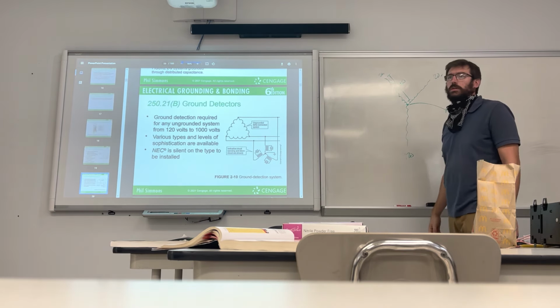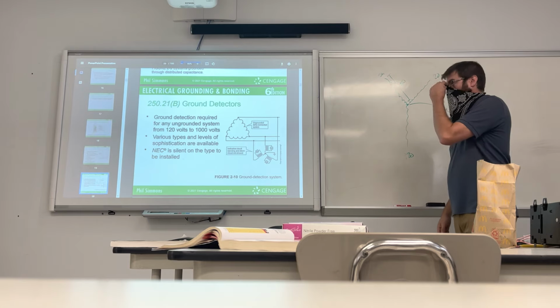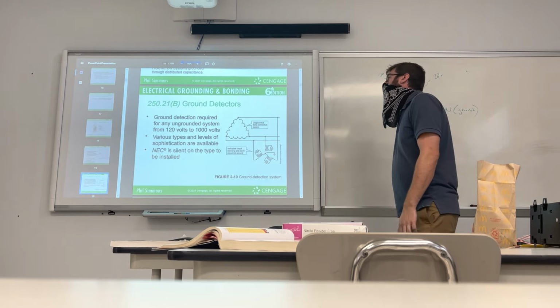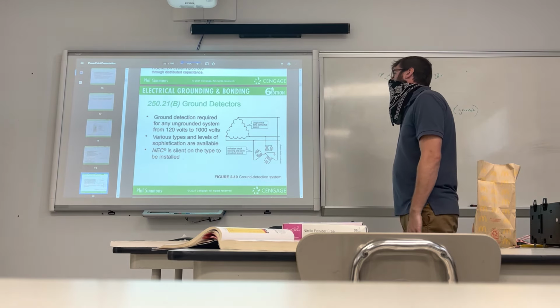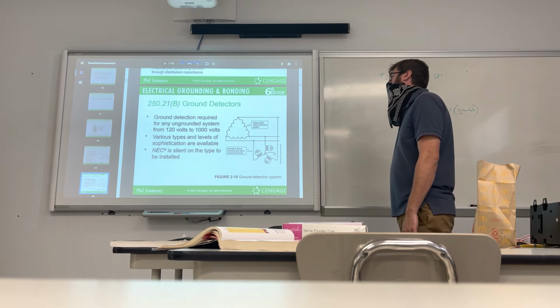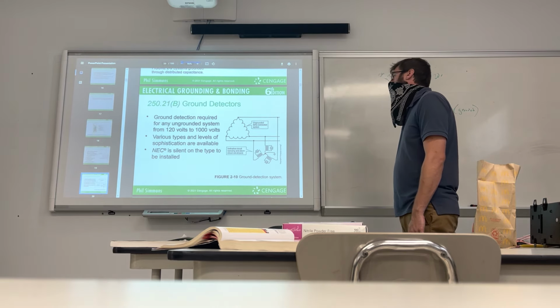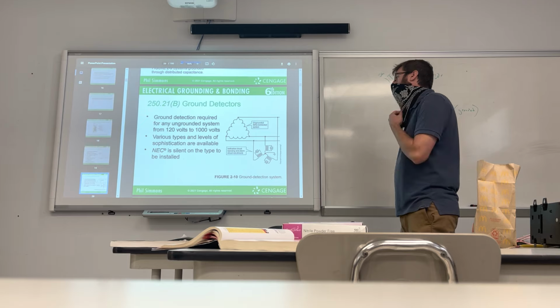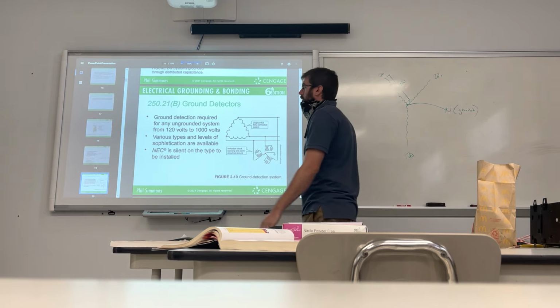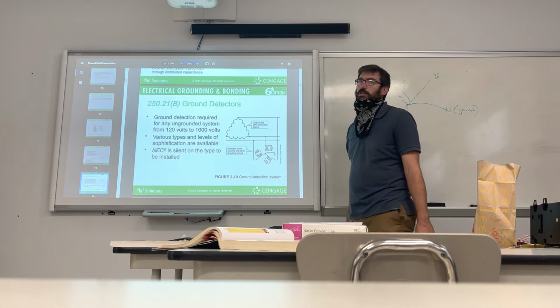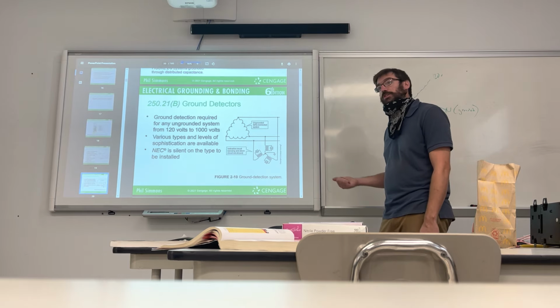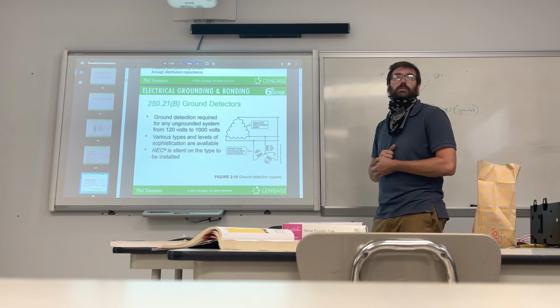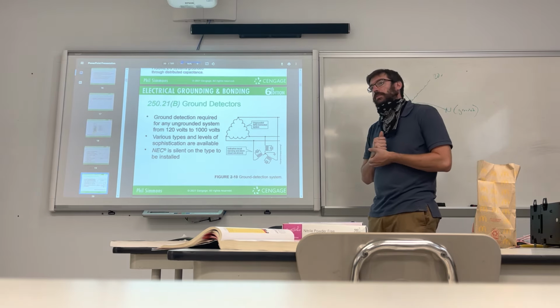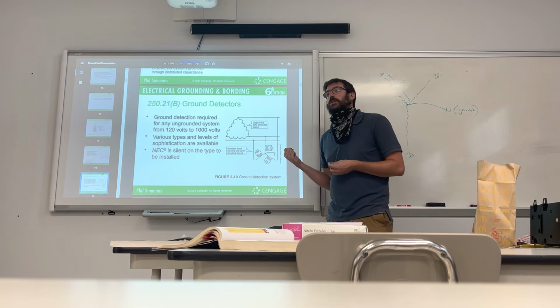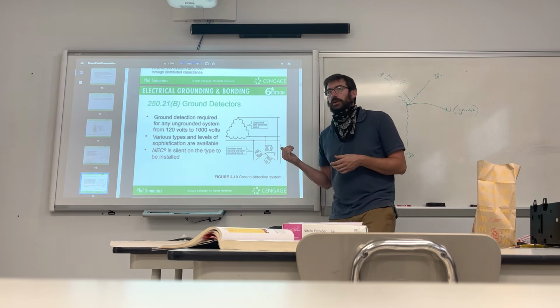Just got the next slide. Ground detection required for any ungrounded system from 120 volts to 1000 volts. Various types and levels of sophistication are available. NEC is silent on the type to be installed. Yeah, and once again, this is a gray area. There's not going to be a whole lot of systems that are ungrounded, but like I mentioned before, say you were supplying the water to all of Scranton, and we just had something ground out. It's still running, but something just ground out.